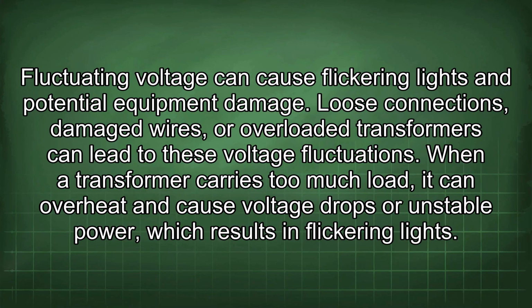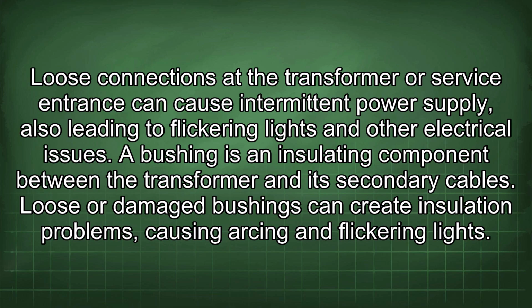Fluctuating voltage can cause flickering lights and potential equipment damage. Loose connections, damaged wires, or overloaded transformers can lead to these voltage fluctuations. When a transformer carries too much load, it can overheat and cause voltage drops or unstable power, which results in flickering lights.